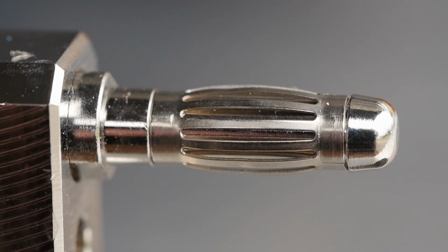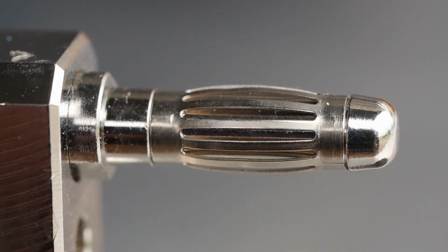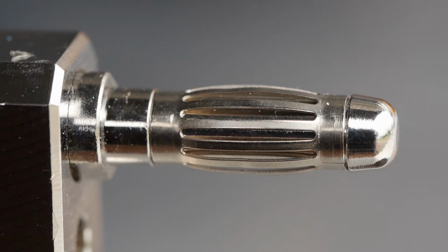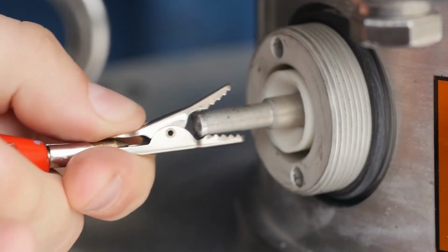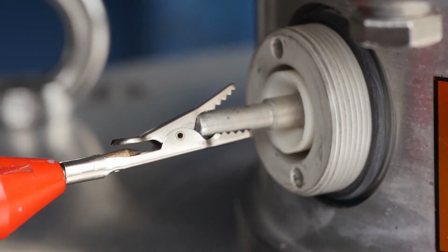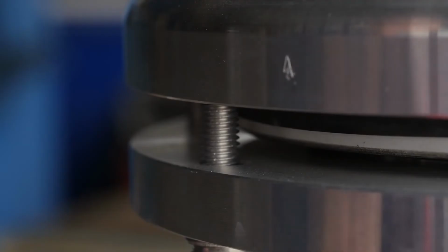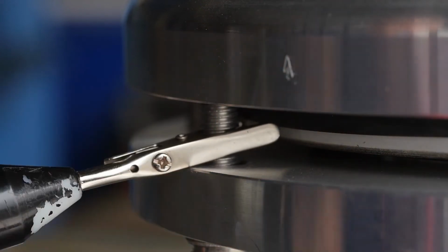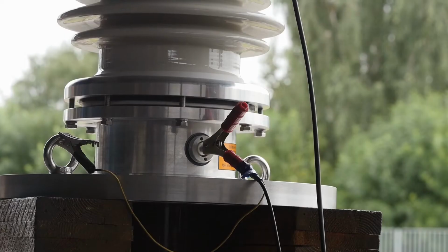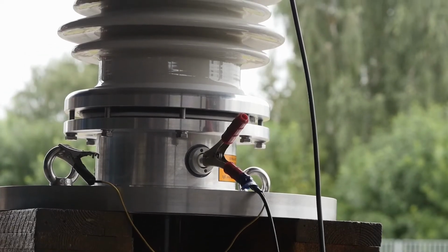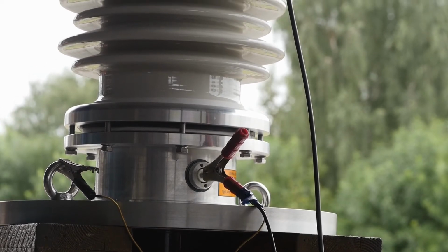After necessary measurements are done, the test tap shall be grounded again. Otherwise, once the high voltage is applied to the bushing, the ungrounded pin of the test tap will have a voltage equal to 50% of the voltage applied to the contact terminal, which will surely damage the test tap, leading to complete failure of the bushing.